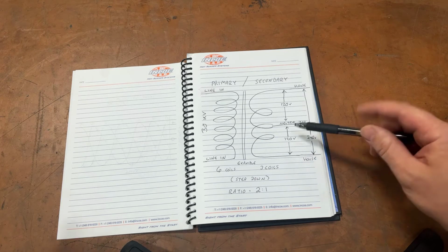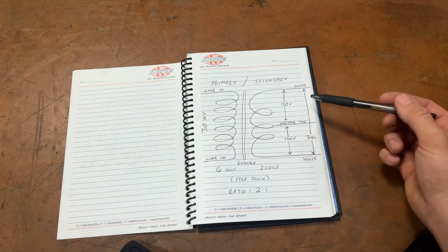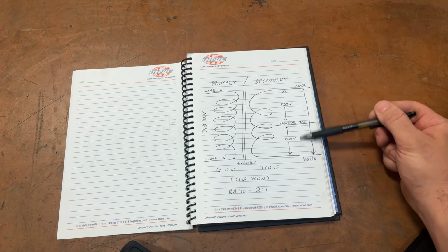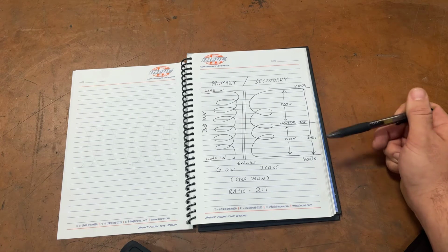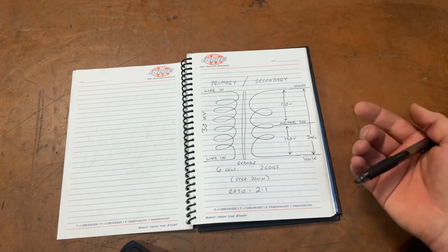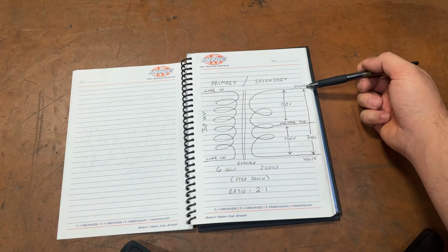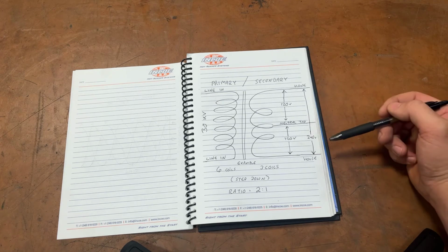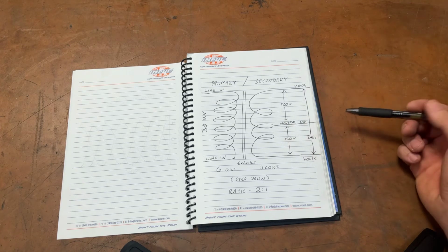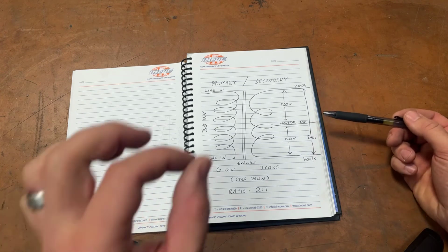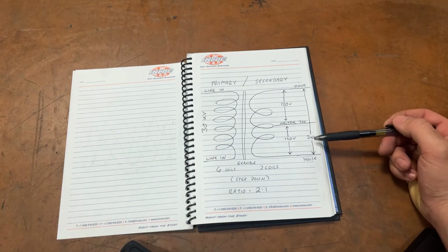So you have the 2 bus bars coming out of your main breaker. One bar is this 120 volts. The other bar is this 120 volts. And whenever you have a breaker that goes across both of those bus bars for like your dryer, your air conditioner, big stuff like that, it utilizes the entire secondary coil. See that? It's not magic. You don't just get an extra 120 volts. You just utilize the entire secondary side of this transformer. Actually, it's amazingly brilliant how this works.